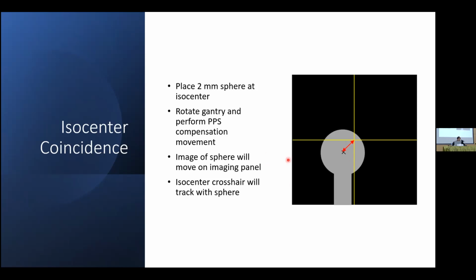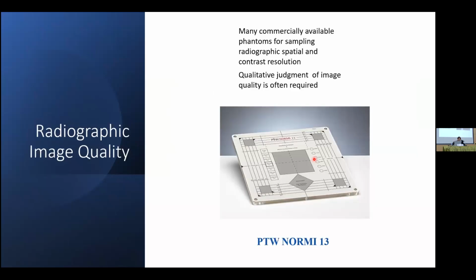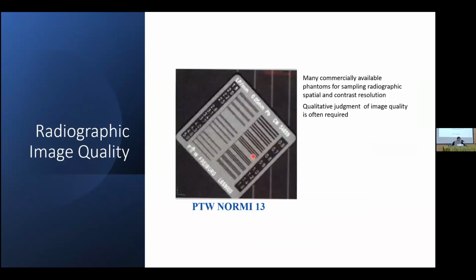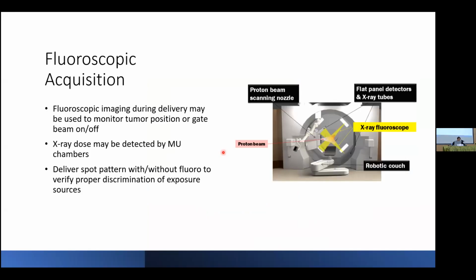So there are different ways to do radiation isocenter, and different ways for the vendor to do radiation isocenter corrections. They each have their pluses and minuses. I like what they do with the steering magnets as opposed to moving the couch. Again, when you're doing imaging, you can use the radiographic here just to do different tests. I think some of you will be familiar with this because you probably do this when you're doing cone beam CT or proton measurements. If your system has fluoro, you've got to be able to do the fluoro tests.